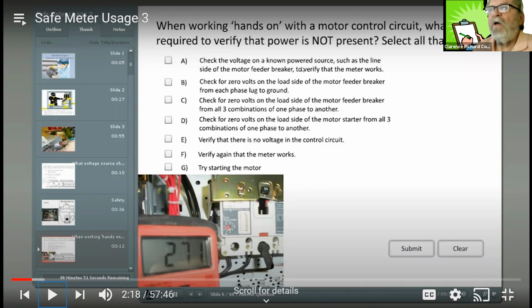And so, how about E? Verify there's no voltage in the control circuit. Yeah, that's important. You could. Verify again that the meter works. Yeah, that's important. How about trying to start the motor? Would that be a good thing to do? No.